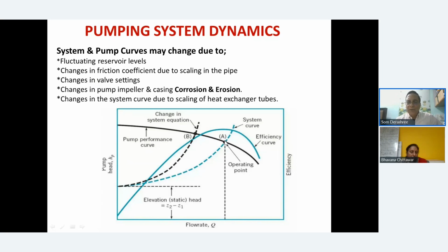Now if you want less flow, then you close the valve. The operating point comes here. But then, you know, the efficiency curve was like this. So because of closing the valve, the efficiency is now a different efficiency, which is at point B. So we have to keep that in mind.